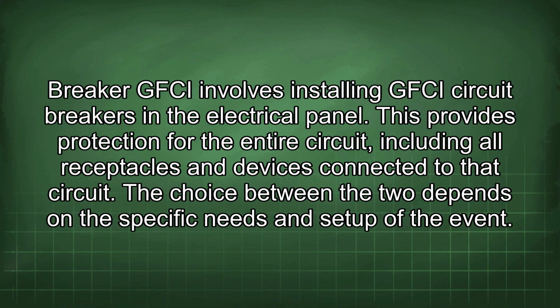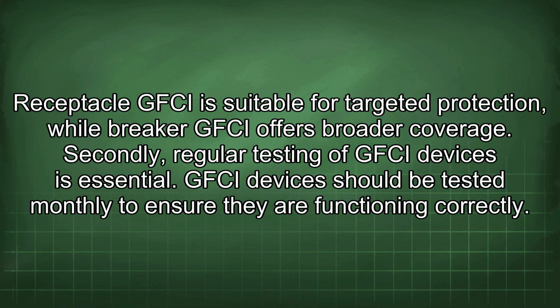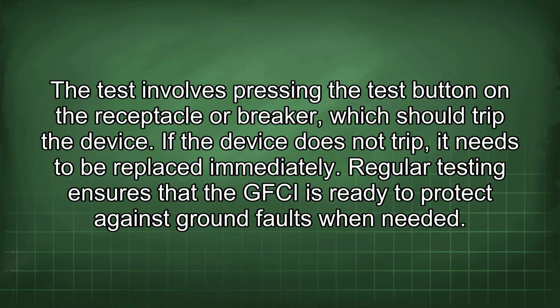The choice between the two depends on the specific needs and setup of the event. Receptacle GFCI is suitable for targeted protection, while breaker GFCI offers broader coverage. Secondly, regular testing of GFCI devices is essential. GFCI devices should be tested monthly to ensure they are functioning correctly. The test involves pressing the test button on the receptacle or breaker, which should trip the device. If the device does not trip, it needs to be replaced immediately. Regular testing ensures that the GFCI is ready to protect against ground faults when needed.